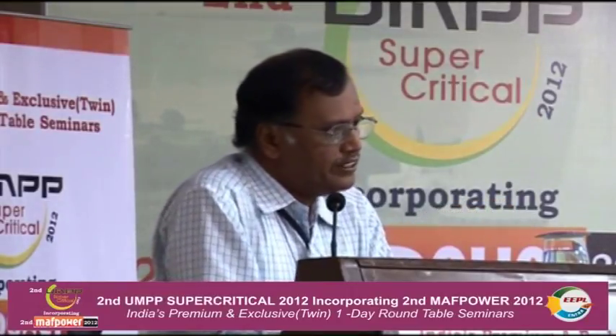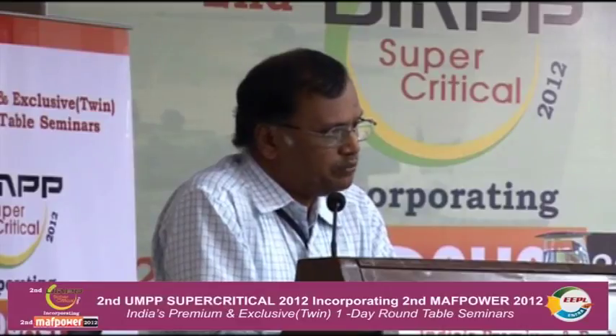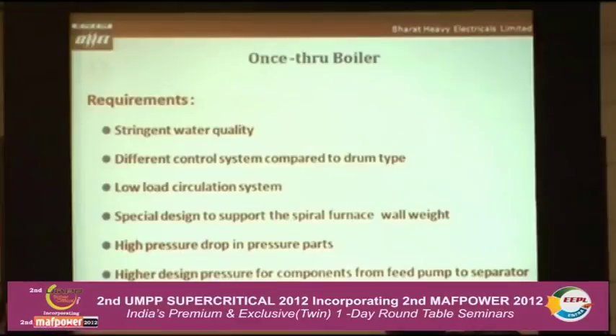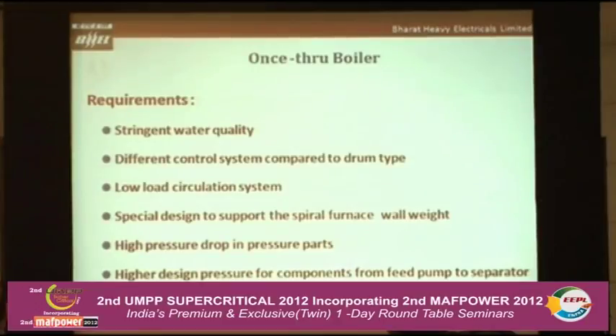So, as I told you earlier, because of the nature of this once through boiler design, stringent water quality is necessary, because once water has entered, it cannot be controlled. And the control system is totally different. In the drum, you are aware, we have a 3-element control, and here it is totally different. The low load circulation system is a new concept used in once through boilers. And again, the spiral design is used. In regular drum type boilers, we have vertical walls. Here it is spiral walls.